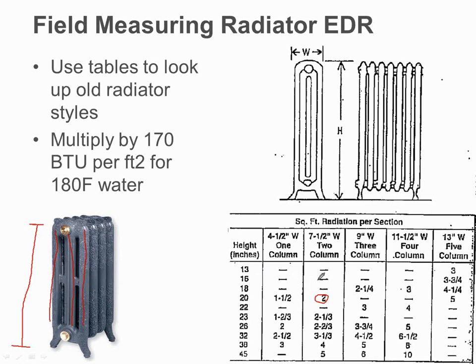So if I did my paint thing, I'd be able to paint out a 2 foot by 4 foot square on the floor. And that's my 8 square feet. Now I take that 8 square feet, times it by 170, and I know what that radiator can put out. So let's just make it easy. Let's say it's 10. We're going to be at 1,700 BTUs. It's a 5-section radiator. So if I got 1,700 BTUs and I try to shove 3,000 in it, what's going to happen? Nothing. I can only get 1,700 out.